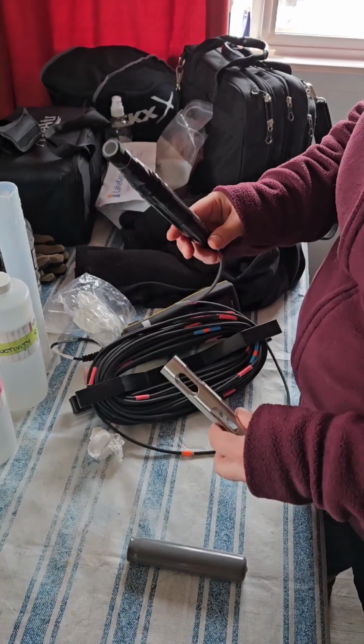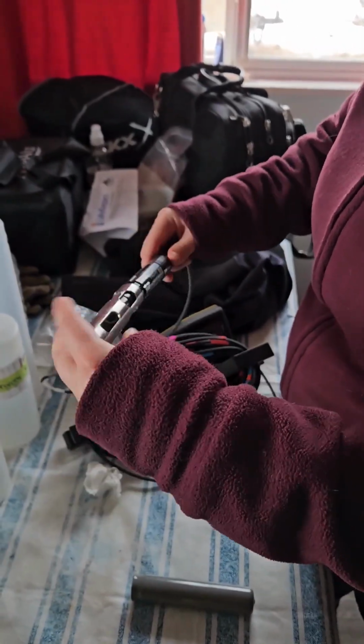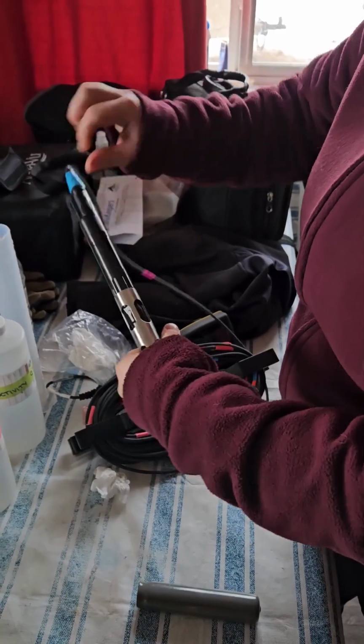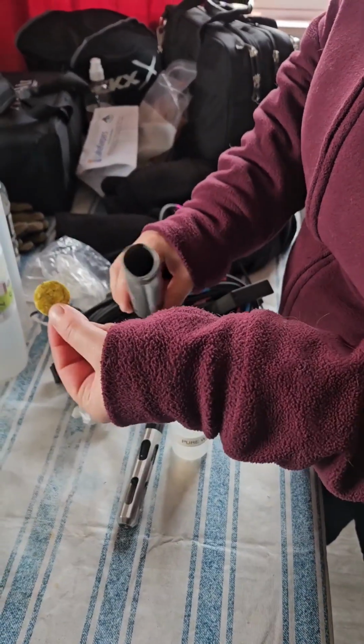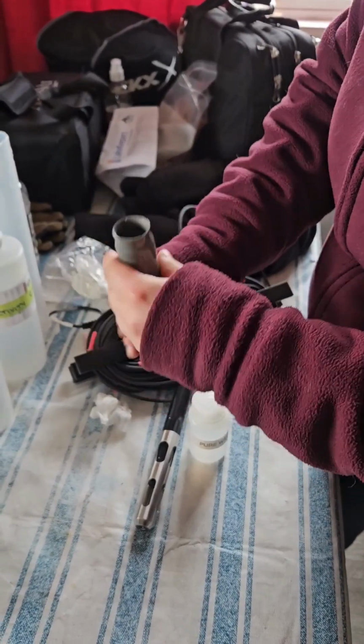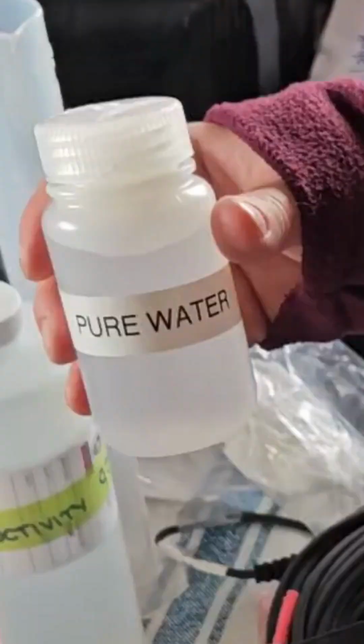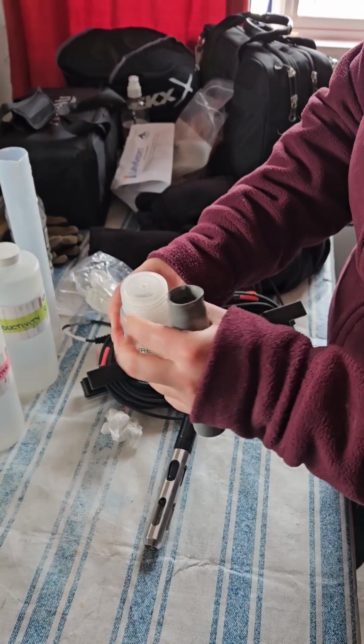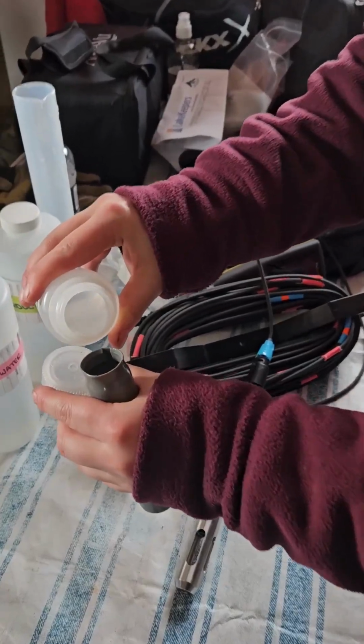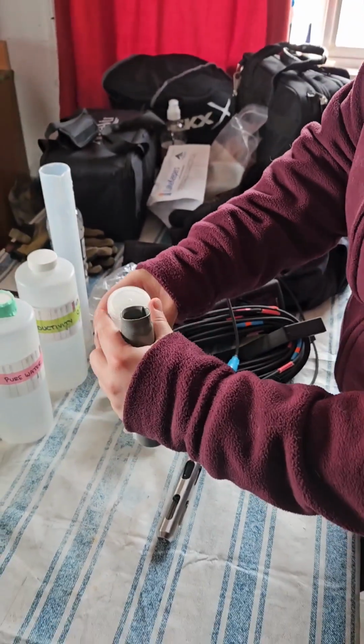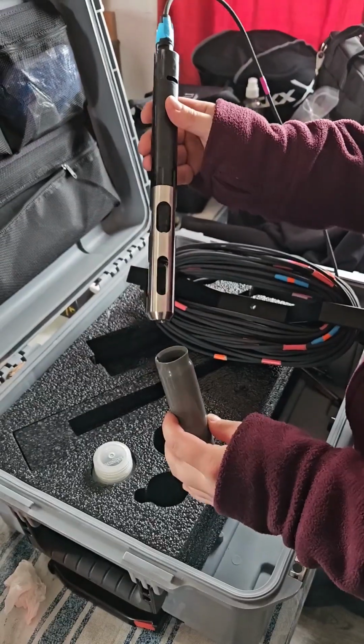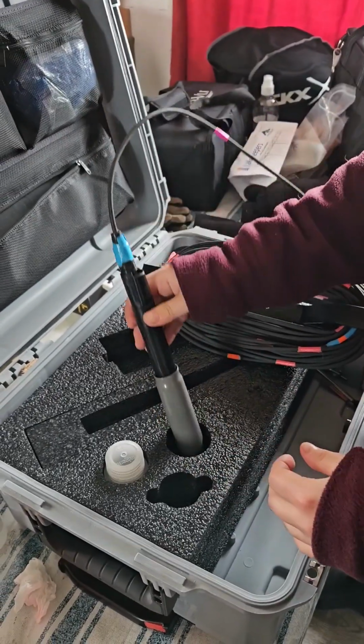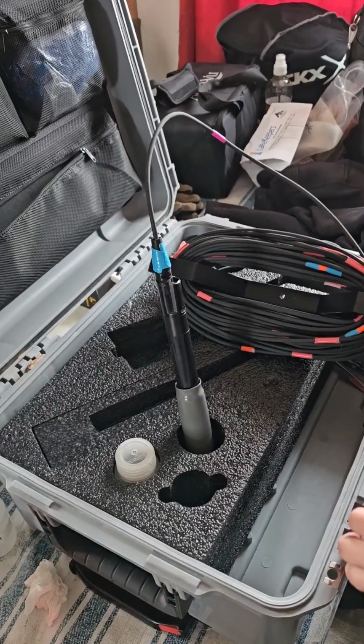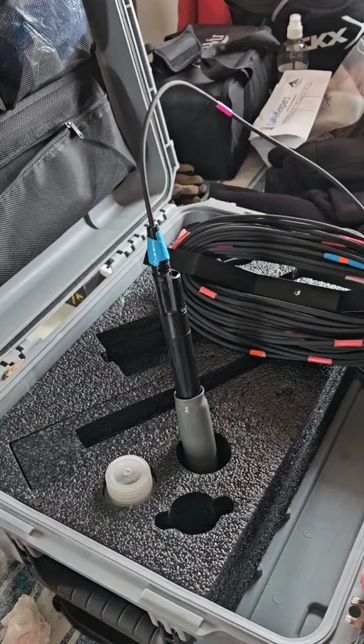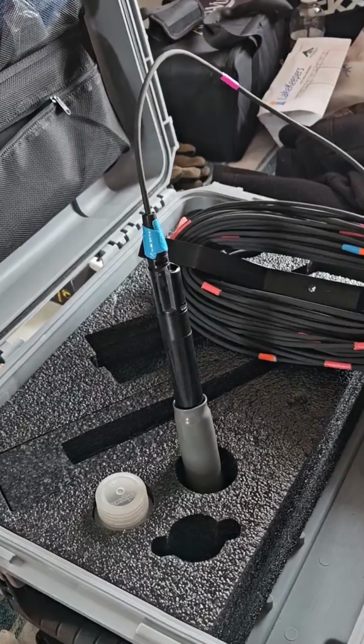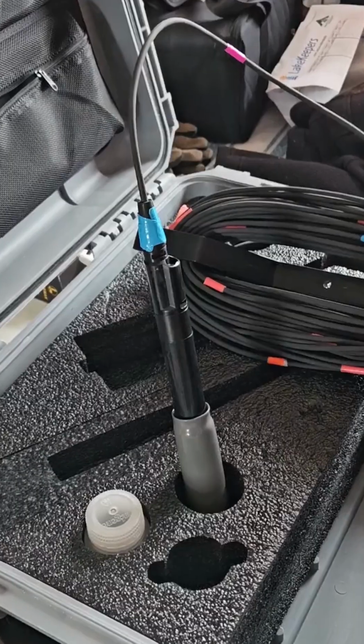Once we've inspected it, we can put the metal guard back on carefully and screw it back on till it's tight. And in the gray sleeve will be a yellow sponge that we'll make sure is in there, and we will put some pure water. You don't need a lot, just a little bit, just to wet the sponge. So once that's on, we will put the gray sleeve back on and stand the probe upright while we begin to calibrate. Allow your probe to stand for about a minute just to allow the probe to acclimate to the moisture from the wet sponge.